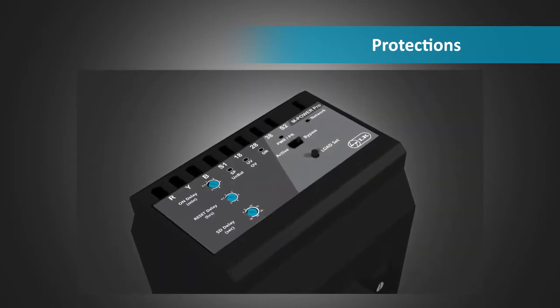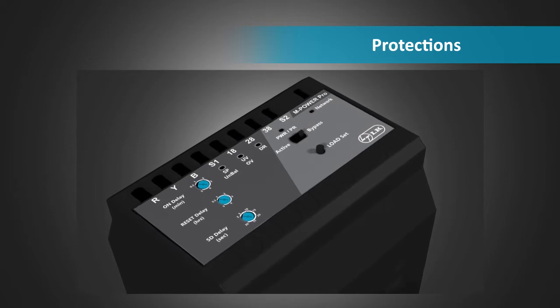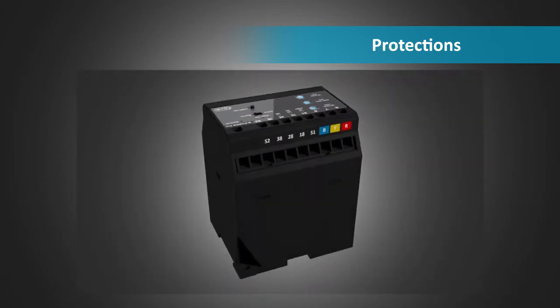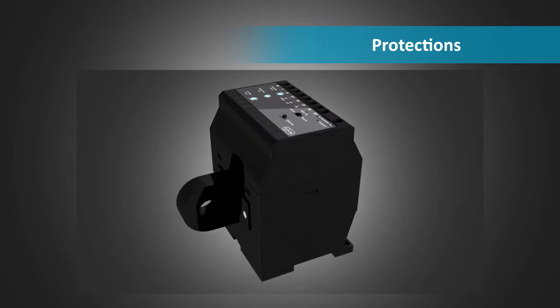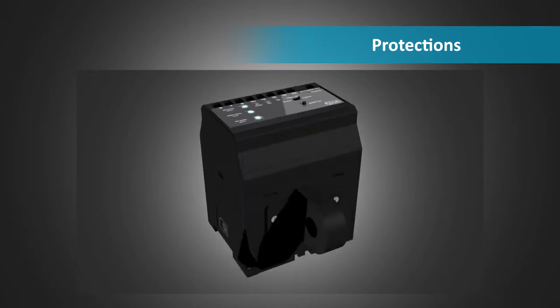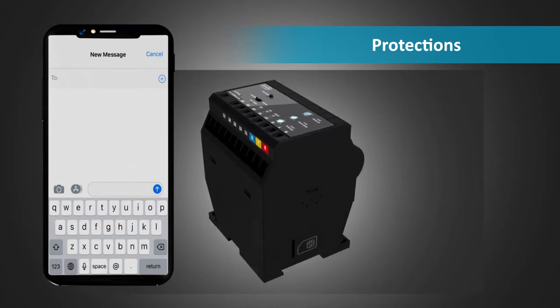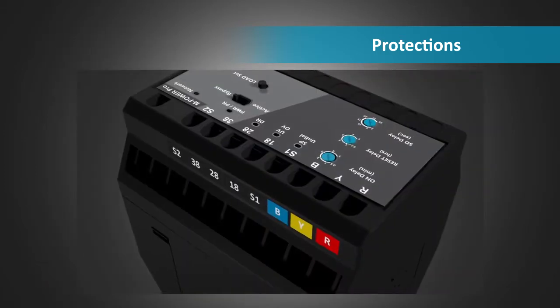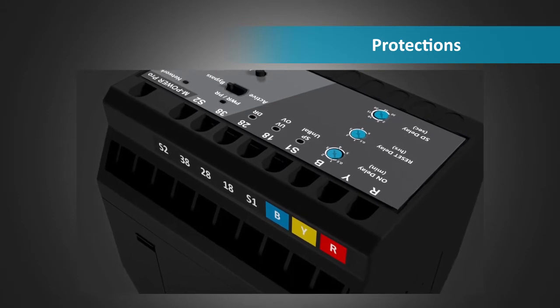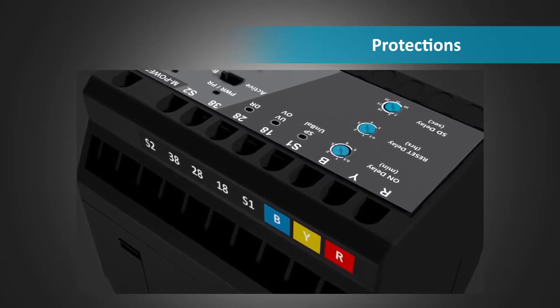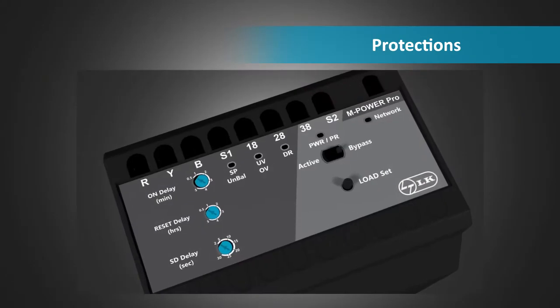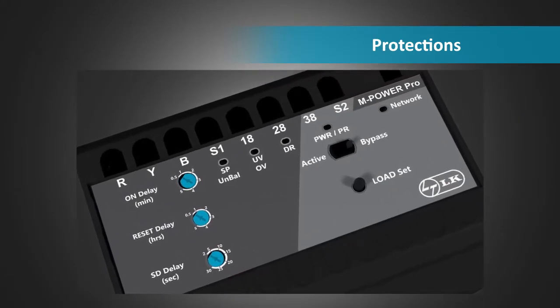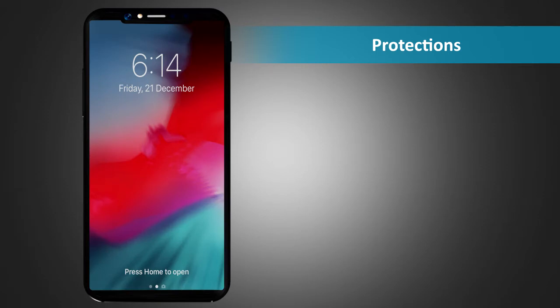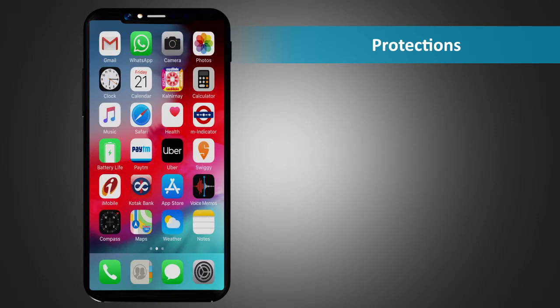Protections. mPower Pro offers a host of protections which are enabled by default. At the same time, it offers the facility to enable or disable each protection independently by sending appropriate SMS. However, whenever any fault is disabled, the unit will not trip, even though the fault exists in the system. There will be no LED indications for the fault. Also, the master and other registered users will not receive any information via SMS from the unit.